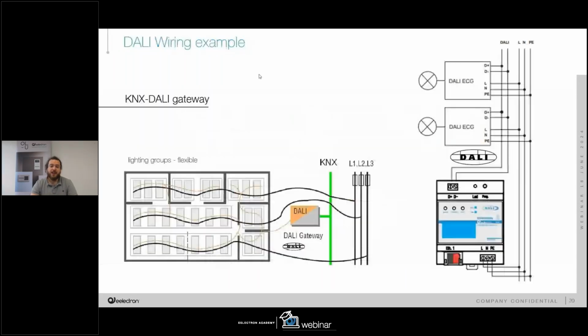In the next slide, we can see an example of wiring where we have, for example, different phases, because in this case we have a three-phase system, and we can wire very easily each lamp with only one DALI bus with the in-out connection between each ballast. And all of them are connected to our KNX to DALI gateway.